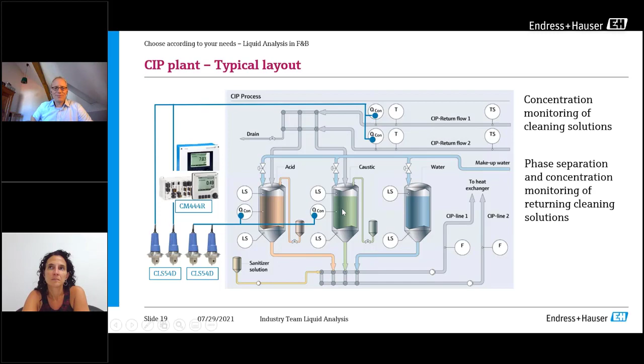On the next slide you see a couple of pictures of the installation. That is for the concentration directly in the tanks for the CIP agents. In the upper right one you see the different vessels. The sensors are installed from the bottom. Here you adjust the acid and base concentration in the tanks, so you need a very accurate measurement, because it has an impact on the cleaning. Is the concentration correct for good cleaning? If you add too low a concentration, the cleaning won't be very good. If you add too much cleaning agent, you waste a lot of money. So it is important at that stage to have a very accurate measurement, which you have with the CLS54D.